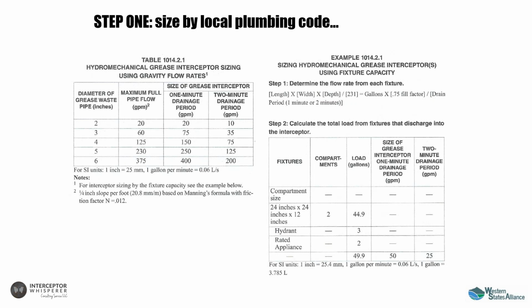So we know developed feet of pipe absorbs a lot of liquid. So normally, outside the building, we would suggest using a 2 minute drainage period. That's what this column over here is for. This is normally outside the building.